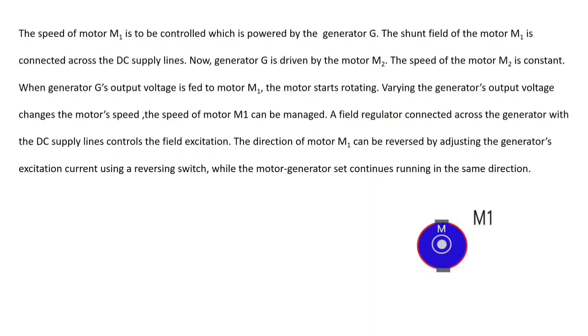The generator is driven by the motor M2, and the speed of motor M2 is constant. The output of the generator is given to M1. A field regulator connected across the generator with the DC supply line controls the field excitation. The direction of motor M1 can be reversed by adjusting the generator excitation current using the reversing switch, while the motor-generator set runs continuously in the same direction.